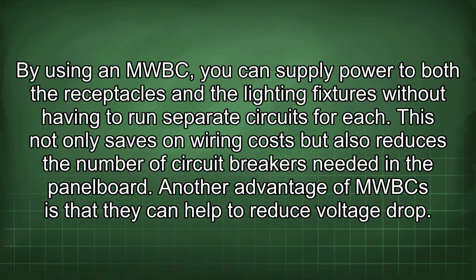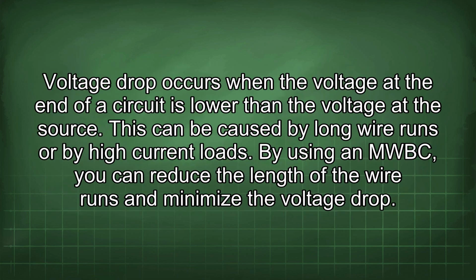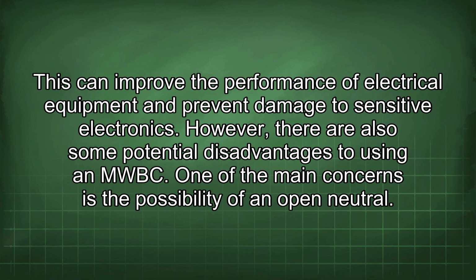By using an MWBC, you can supply power to both the receptacles and the lighting fixtures without having to run separate circuits for each. This not only saves on wiring costs but also reduces the number of circuit breakers needed in the panel board. Another advantage of MWBCs is that they can help to reduce voltage drop. Voltage drop occurs when the voltage at the end of a circuit is lower than the voltage at the source. This can be caused by long wire runs or by high current loads. By using an MWBC, you can reduce the length of the wire runs and minimize the voltage drop. This can improve the performance of electrical equipment and prevent damage to sensitive electronics.